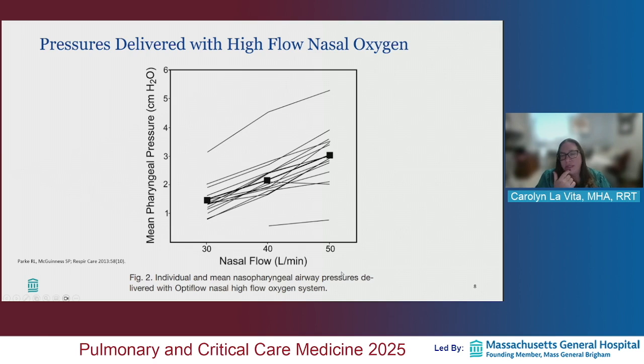Often we're asked to put high flow nasal cannula on for the PEEP effect. And I will just caution you with this. There certainly is, because of the high flow within the system and because of the fitting of the prongs, they're a wider prong and they fit more snugly in the nare, pressure can develop. The question is, is that pressure actually transmitted in a meaningful way, in a therapeutic way? This study that was done 10 years or so ago now looked at pharyngeal pressure, which is probably the best that we can do. And at what flow rates develops which pressure.